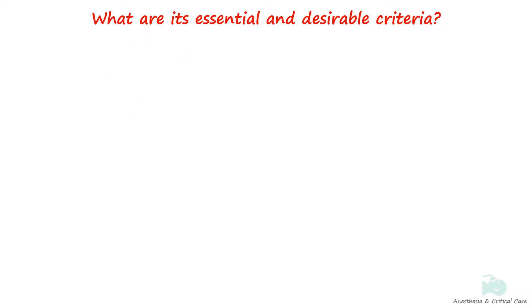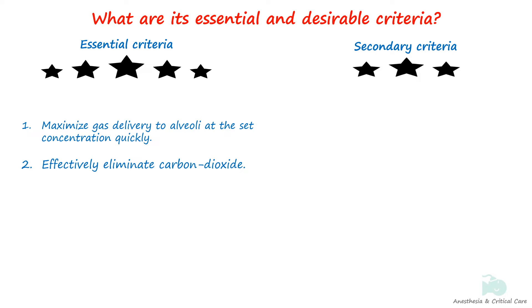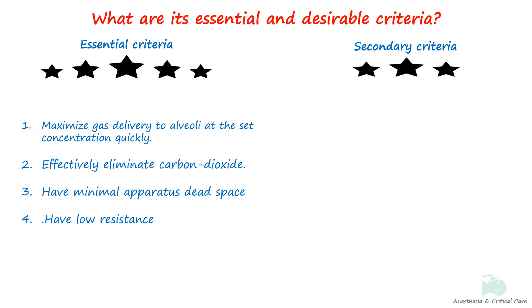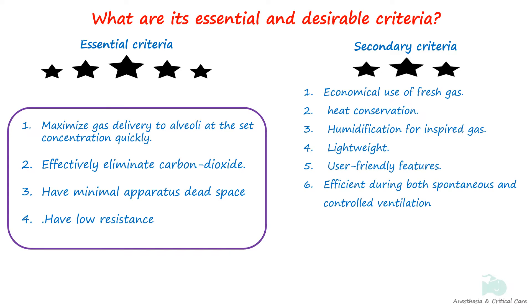The breathing system must perform certain important functions. Some of these are must-have while others are desirable. Essentially, the breathing system must efficiently transport gases from the machine to the alveoli at the desired concentration and in the shortest time possible. Secondly, it should effectively remove carbon dioxide. Thirdly, it should minimize apparatus dead space and maintain low resistance. In addition to these primary criteria, there are other desirable requirements for your reading pleasure.